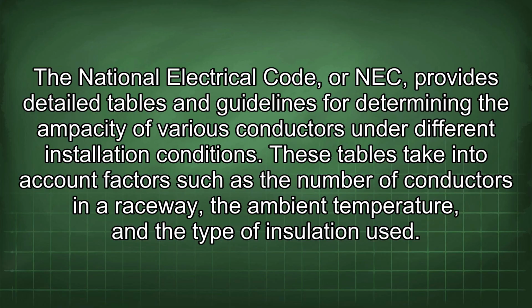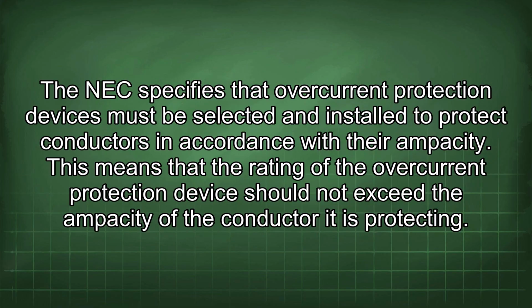These tables take into account factors such as the number of conductors in a raceway, the ambient temperature, and the type of insulation used. The NEC specifies that overcurrent protection devices must be selected and installed to protect conductors in accordance with their ampacity. This means that the rating of the overcurrent protection device should not exceed the ampacity of the conductor it is protecting.